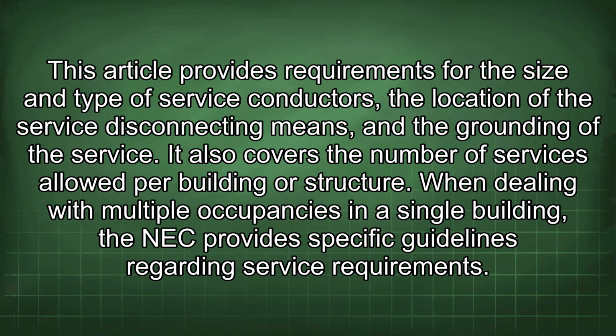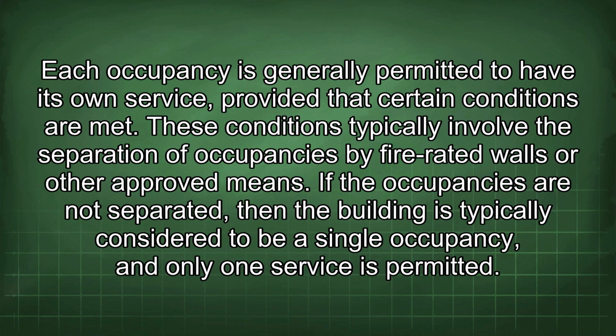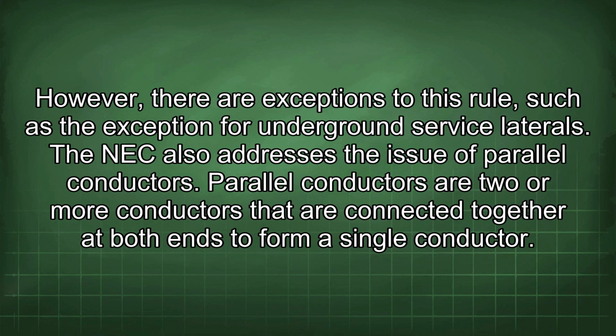When dealing with multiple occupancies in a single building, the NEC provides specific guidelines regarding service requirements. Each occupancy is generally permitted to have its own service provided that certain conditions are met. These conditions typically involve the separation of occupancies by fire-rated walls or other approved means. If the occupancies are not separated, then the building is typically considered to be a single occupancy and only one service is permitted. However, there are exceptions to this rule, such as the exception for underground service laterals.